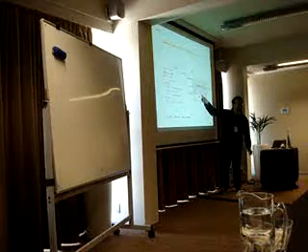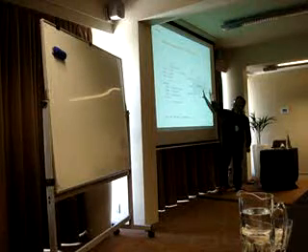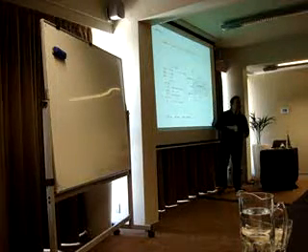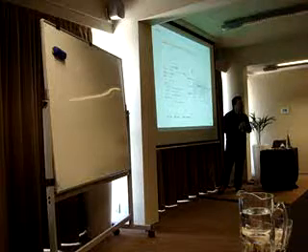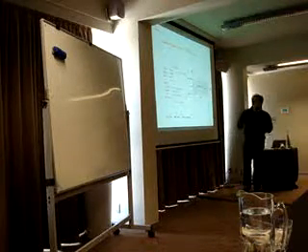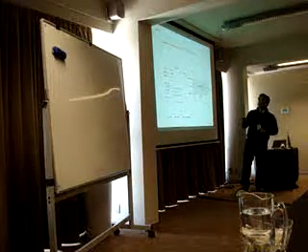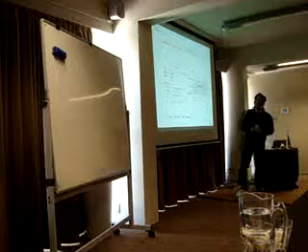If it is strictly smaller than that, you will set it to be false. Otherwise, if you're within this region, there's simply no change, it's just equal to the value in the previous state. Okay, that's the hysteresis function block. It's a basic function block.